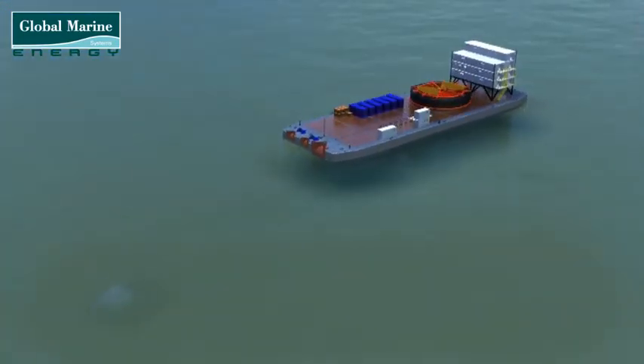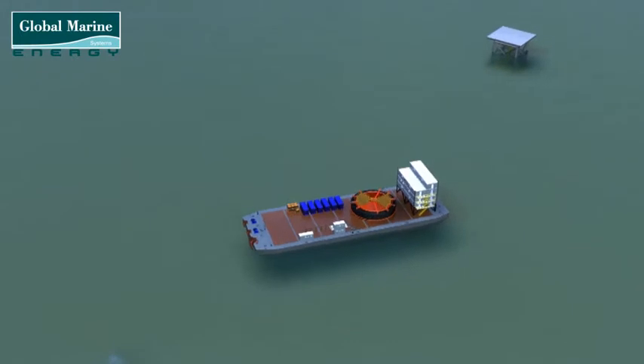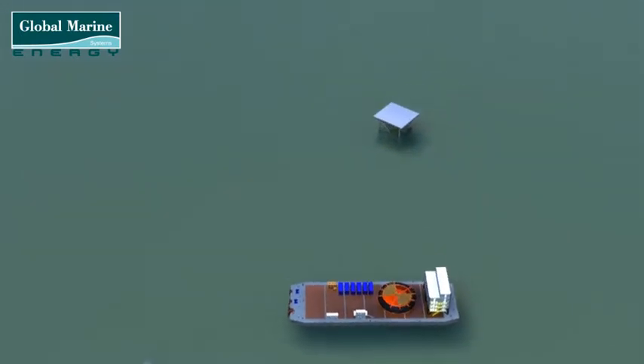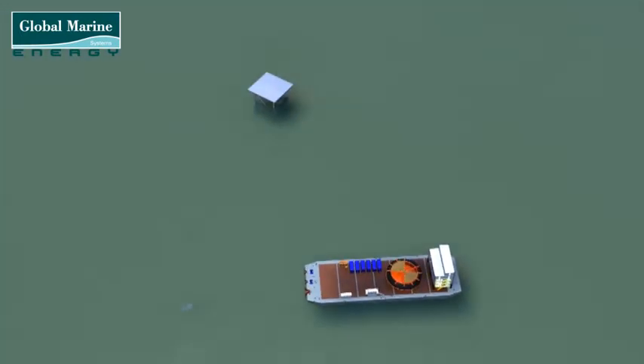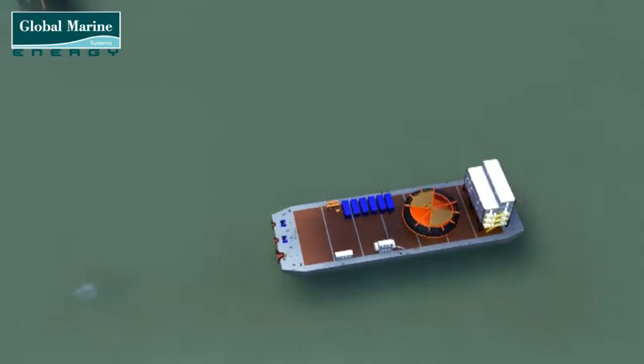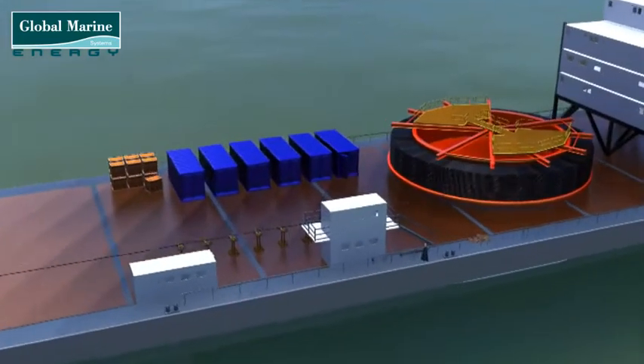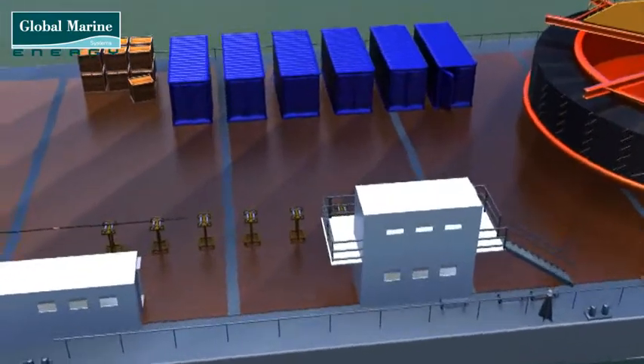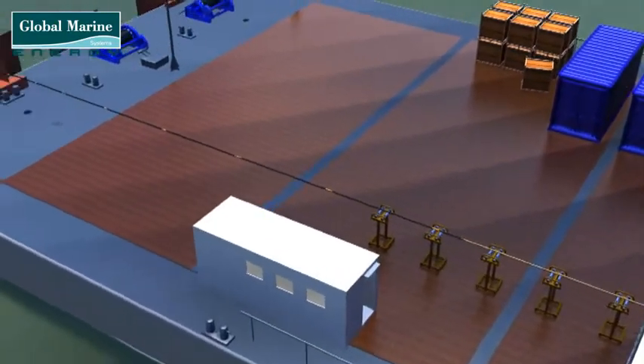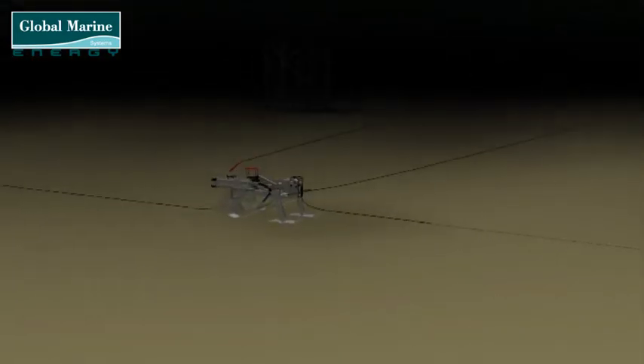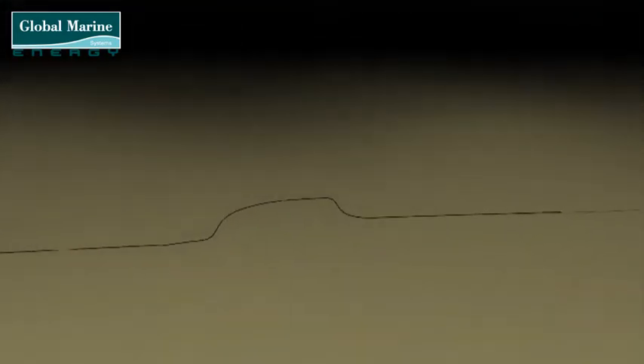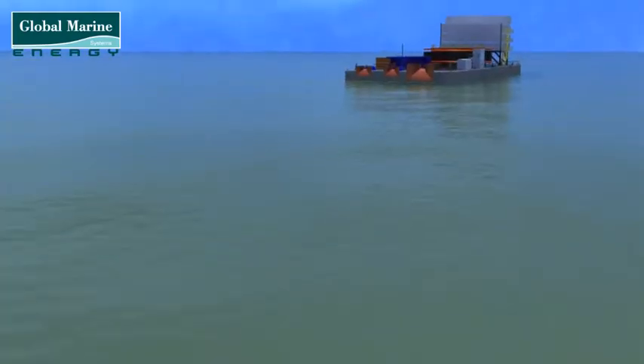The barge continues to lay cable down onto the seabed, drawing the plough along behind it until it reaches a point close to the cable end. At this point, the cable is cut on board the barge and replaced with a rope. Once the plough reaches the rope section, it is recovered to the barge and the cable recovery process begins, taking the barge back to its original position where the cable burial stopped.